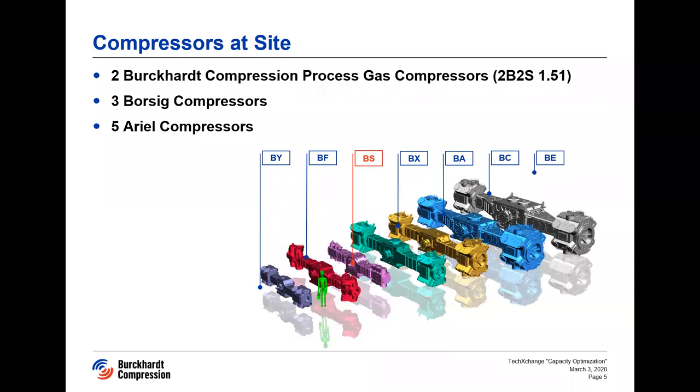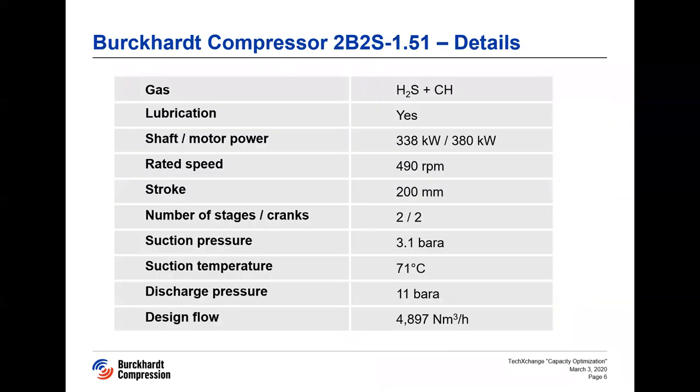The main reciprocating compressors used by this client are two Burckhardt process gas compressors, five Ariel compressors, and three Borsig compressors. The BS Burkhard compressor is a two-stage, two-crank lubricated machine running on wet H2S gas mixture. It has a stroke of 200 millimeters and speed of 490 rpm. With a suction pressure of 3.1 bar absolute and discharge pressure of 11 bar absolute, it compresses gas of approximately 5,000 norm cubic meters per hour. The shaft and rated motor power are 338 kilowatt and 380 kilowatt respectively.